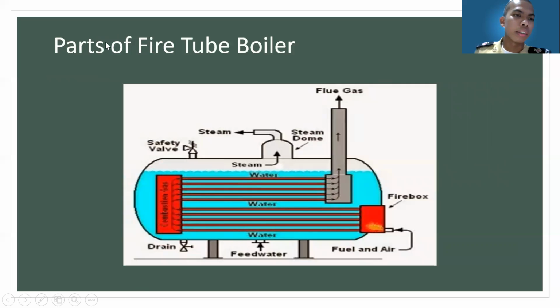Today, these are the parts of the fire tube boiler. The parts of the fire tube boiler include the safety valve. Safety precautions must be taken to prevent any loss, as water at high pressure contains a lot of energy. So, for safety reasons, a safety valve must be installed on the boiler. When the pressure is above the specified limit, the safety valve will open. A minimum of two safety valves are to be provided.